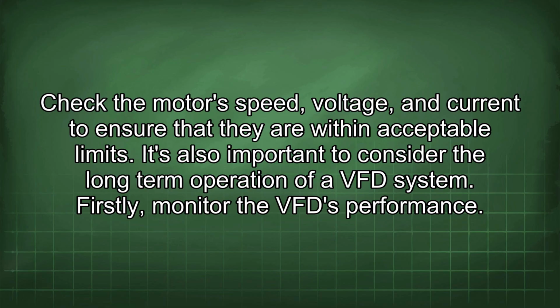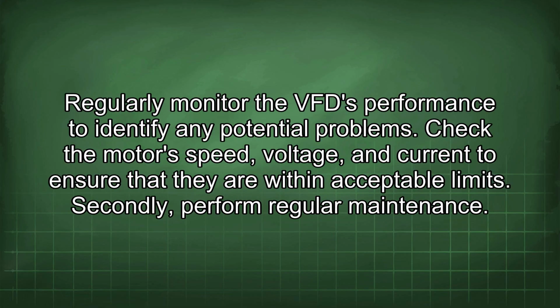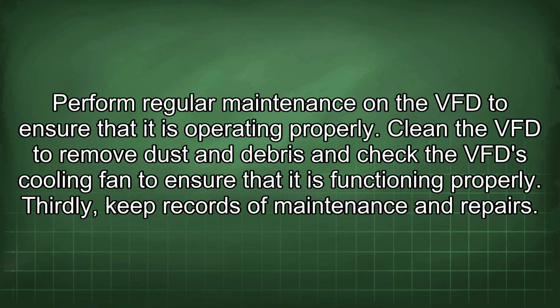It's also important to consider the long-term operation of a VFD system. Firstly, monitor the VFD performance. Regularly monitor the VFD performance to identify any potential problems. Check the motor's speed, voltage, and current to ensure that they are within acceptable limits. Secondly, perform regular maintenance. Perform regular maintenance on the VFD to ensure that it is operating properly. Clean the VFD to remove dust and debris and check the VFD cooling fan to ensure that it is functioning properly. Thirdly, keep records of maintenance and repairs.